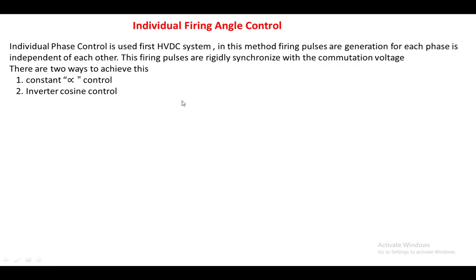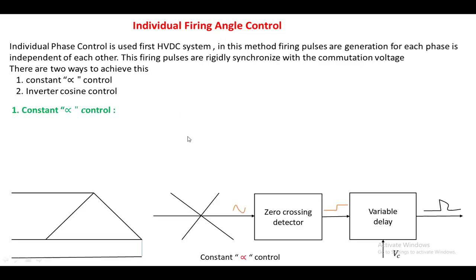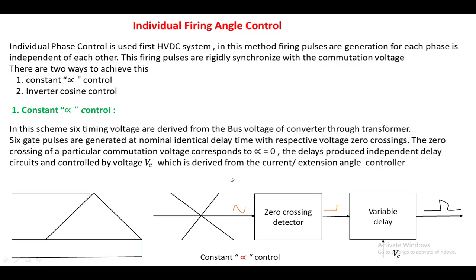Now we will look at constant alpha control. This block diagram shows how constant alpha control is generated. A transformer is connected to the buses before the converter so that we obtain six line voltages. These six line voltages are fed to a zero crossing detector, whose main function is to generate pulses whenever the voltage crosses zero. Based upon the control voltage Vc, the firing pulse will be generated to the respective valve. In this manner, pulses are generated to the valve in constant alpha control.